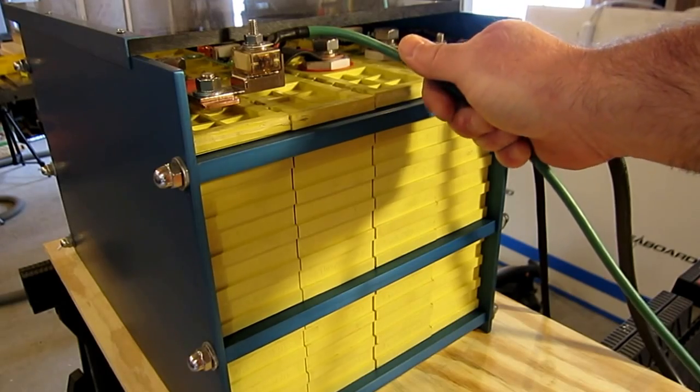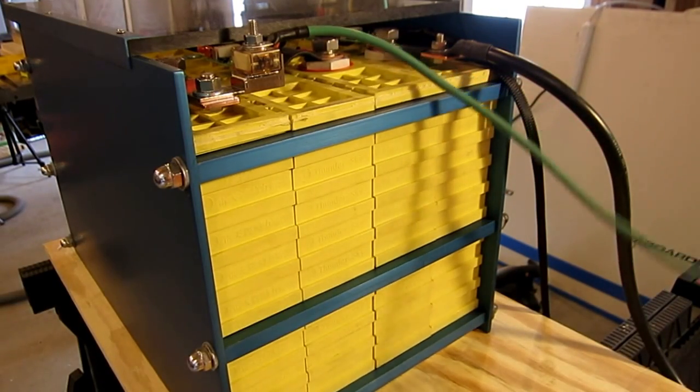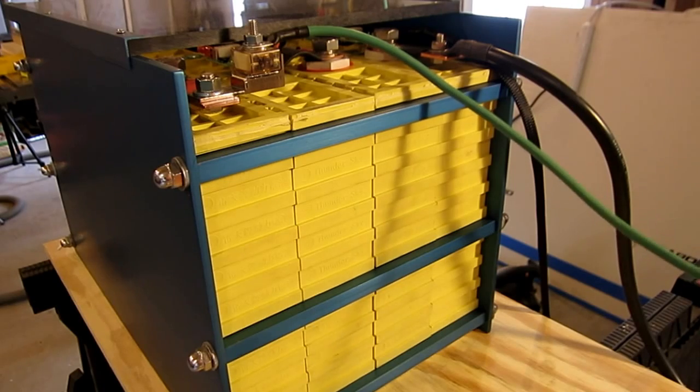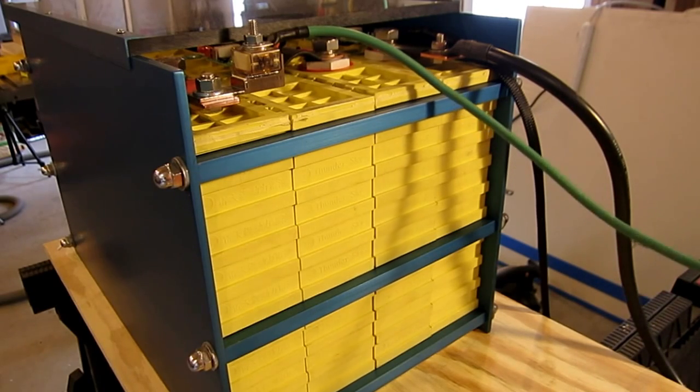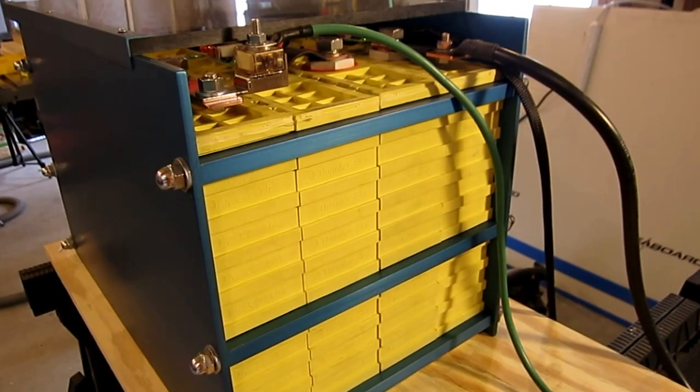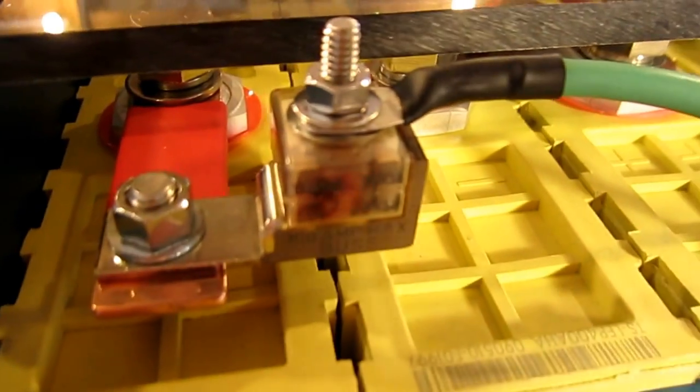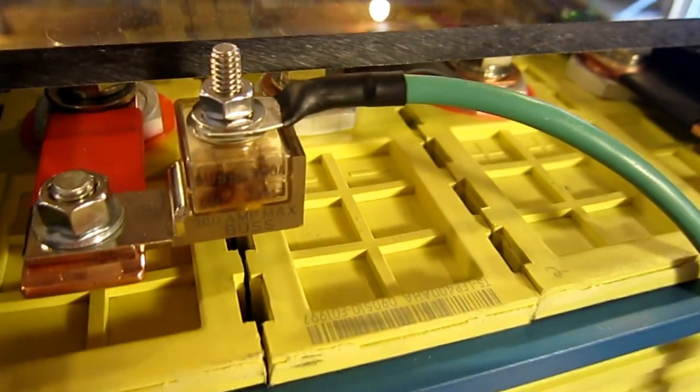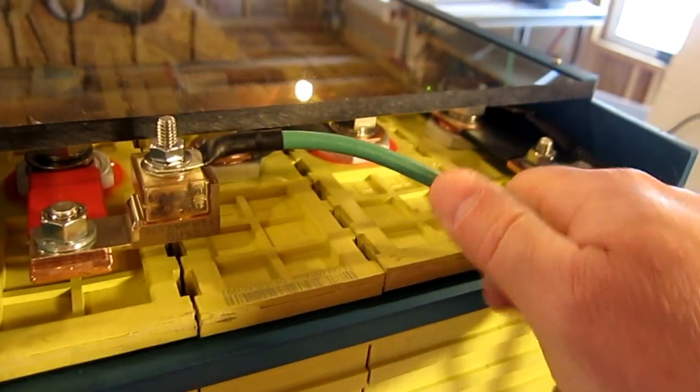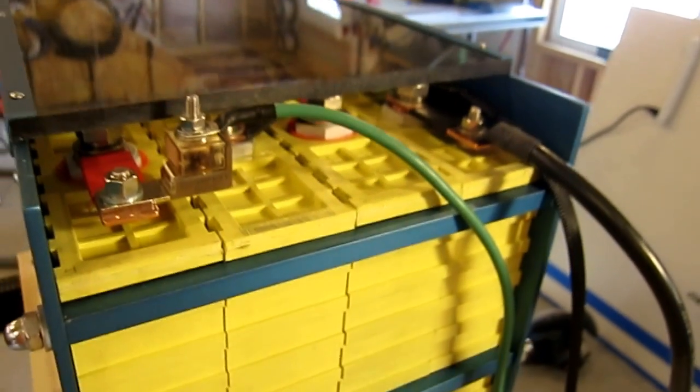This wire is not even warm to the touch. I'm not seeing any signs of melting. I'm going to remove the camera from the tripod here. As we can see, we just destroyed that fuse. What we're trying to protect with these battery bank fuses is the wire.